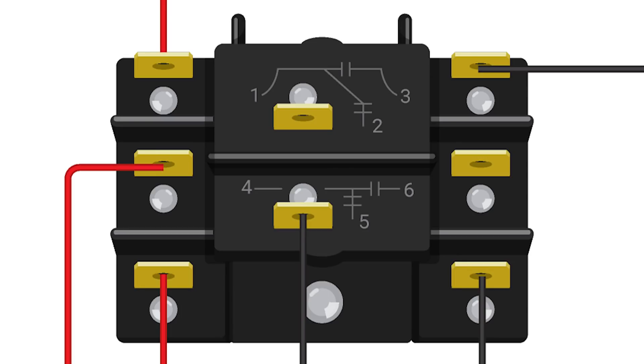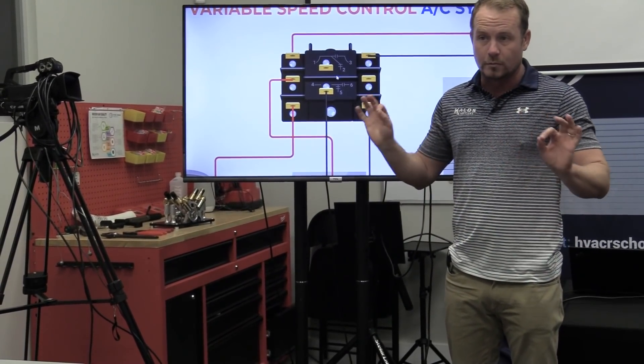In this relay, you have two sets of contacts, and they have both normally open and normally closed positions, which means that when the electromagnet is not energized, you don't have 24 volts applied across it, then this set of contacts from four to five is normally closed. So if I took an ohmmeter and put it right here, it'd beep without being energized. It's normally closed.